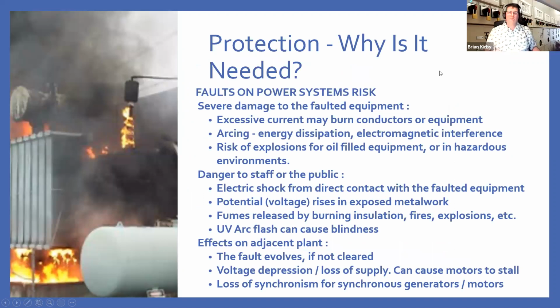So if you have a fault, it can lead to quite severe consequences if your protection either does not operate or is not properly configured. You can see here on the left a transformer fire, where if you allow the transformer to overheat, particularly oil-filled transformers, they can cause explosions and various other incidents. Excessive currents may also cause conductors to burn or anything attached to it. You may get arcing, which will dissipate energy into adjacent equipment and also may interfere electromagnetically with other equipment. And if you've got other hazardous or explosive materials nearby, you can cause explosions with them as well.